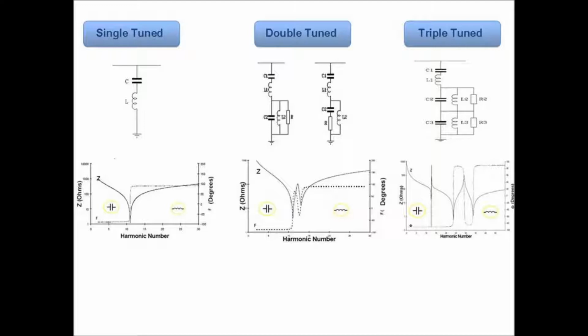These are the single tuned, double tuned and triple tuned. It's basically just putting additional circuits in parallel, and you can see that the single tuned brings a nice low resonance, so you've got the series resonance. At whatever point you had your parallel, you'll be able to cancel them out and you'll end up with not many problems there. The double tuned has got two resonances, and it tends to work if you needed to do two fairly close by harmonics. Not so great for very spread out ones. You might be better off just building two single tuned close by.